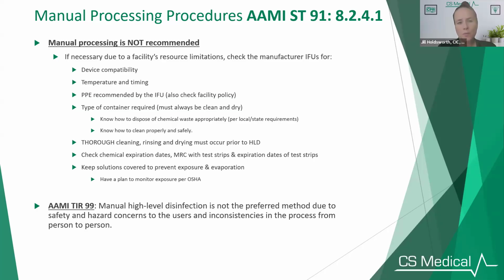The rinsing is so important because you have just soaked that probe in a container of harsh chemicals for a long time. And the chemical needs to be rinsed per whatever the IFU says, which sometimes can be 2 minutes, 4 minutes, and then you have to do it again. Some of this says that you must have critical water. Do you have critical water where you're doing this? And if you don't, you're not going by the IFUs. Even if you don't have critical water, are you able to spend the time to rinse for 2 straight minutes twice? Are you actually going to do that?